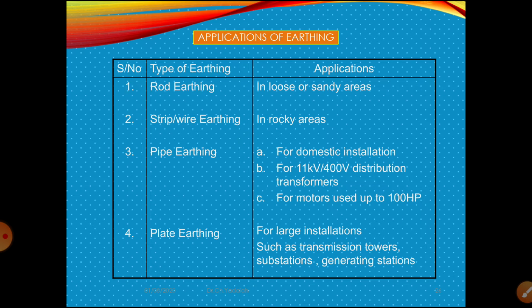We use pipe earthing for distribution transformers, and for motors up to 100 HP in our industries and laboratories. Plate earthing is preferred for large installations such as transmission towers, substations, and generating stations, using copper plate earthing, dear students.